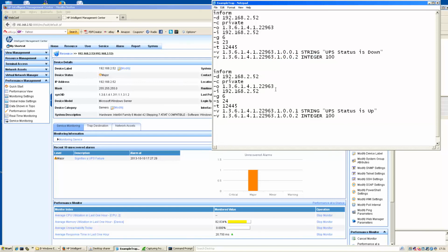I will then configure this trap, the second one down here. Again, I'm going to specify that I want to use that as the key set parameter, and then I'm going to convert this trap to an alarm, so I need an alarm for both cases. And then what will happen is when we get this alarm coming in and then we get this alarm, if this alarm has the same varbind value in this case, then it will acknowledge it or delete it.